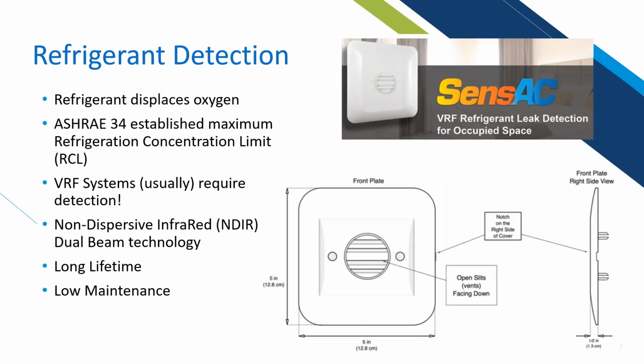And along those lines, if you're doing a project that we were talking about earlier, and this would be especially useful in a VRF application, we have refrigerant leak detection available as well. ASHRAE 34 has established a refrigerant concentration limit, and VRF systems usually require detection. This is a great insurance policy for your owner end user, and it's definitely something worth considering putting into a space where gas refrigerant can build up and become a problem.